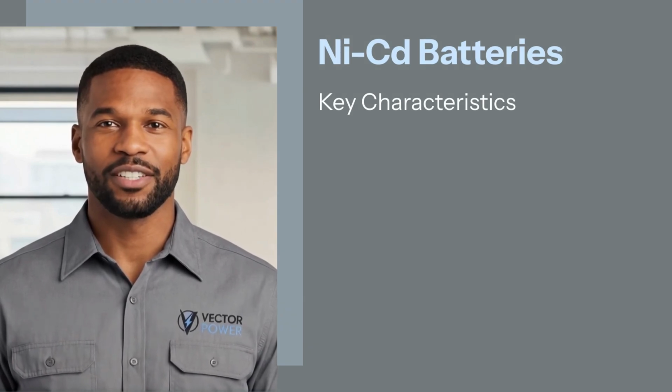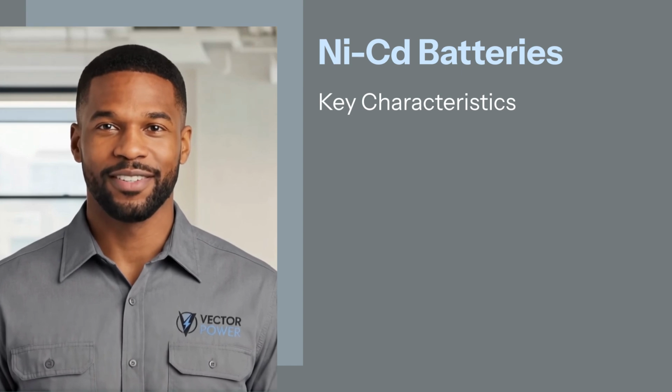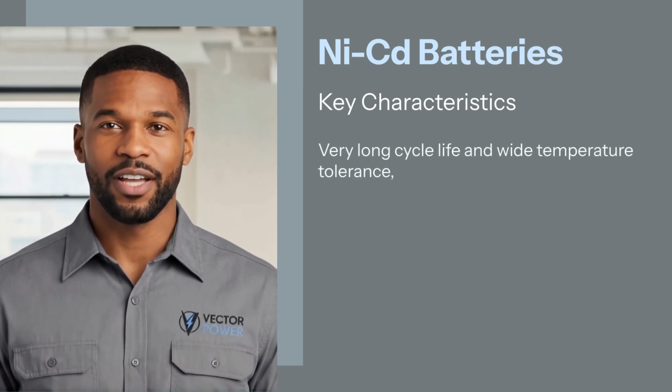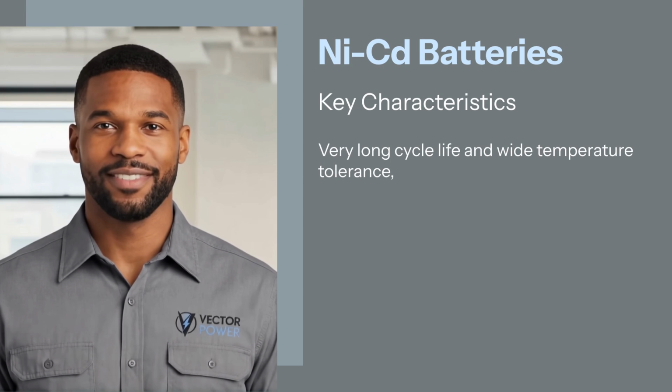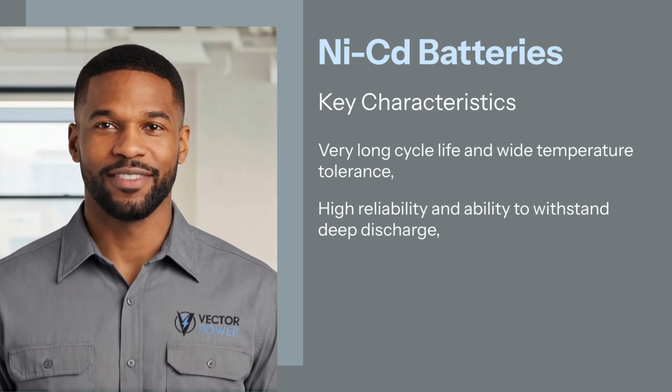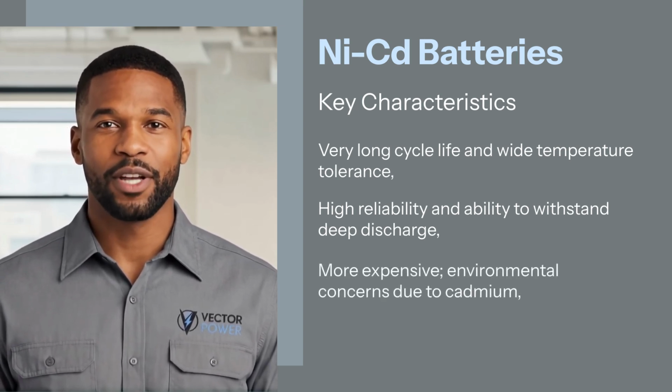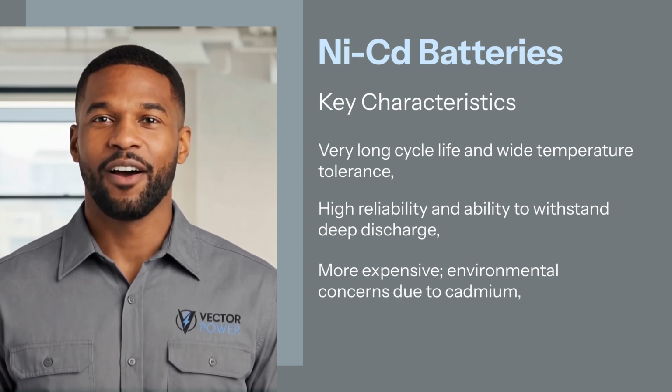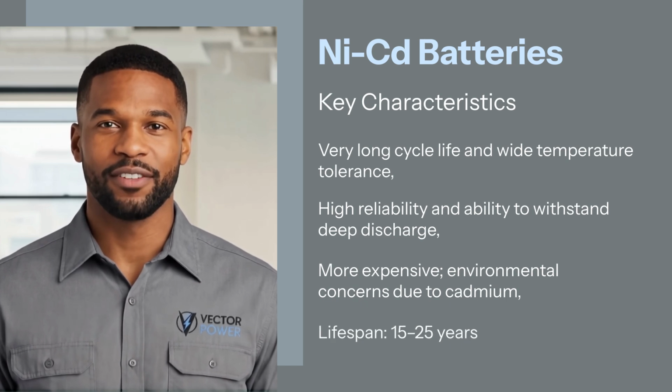Key characteristics of nickel-cadmium batteries include very long cycle life and wide temperature tolerance, high reliability and ability to withstand deep discharge, more expensive plus environmental concerns due to cadmium, and a lifespan of 15 to 25 years.